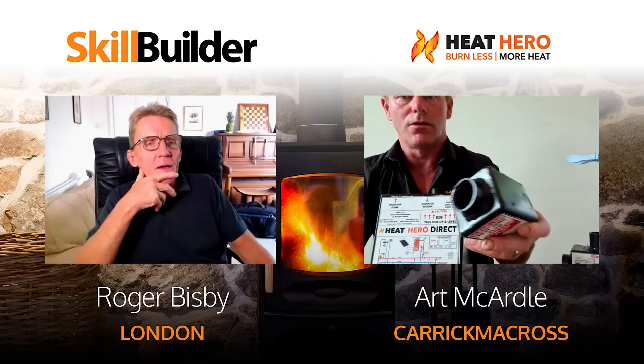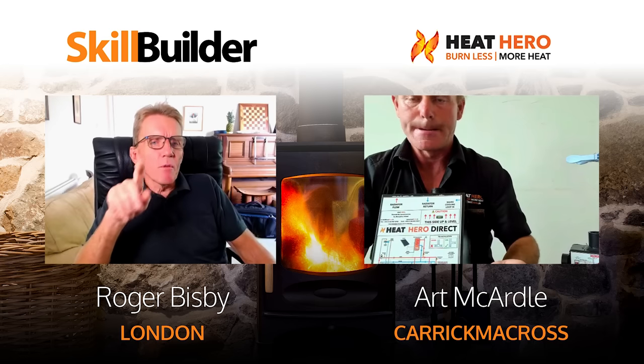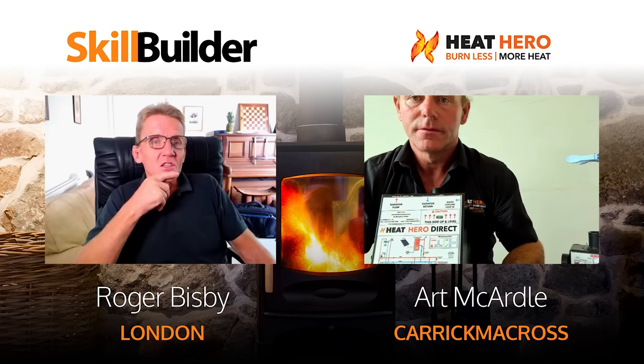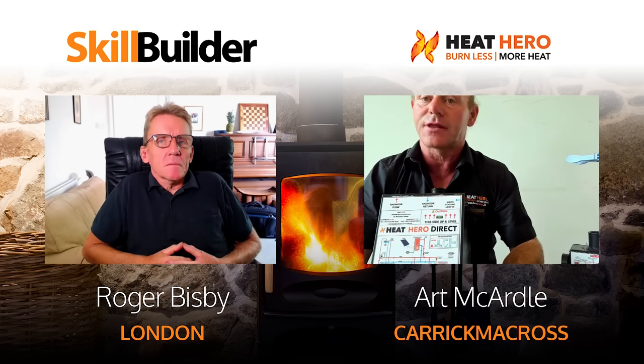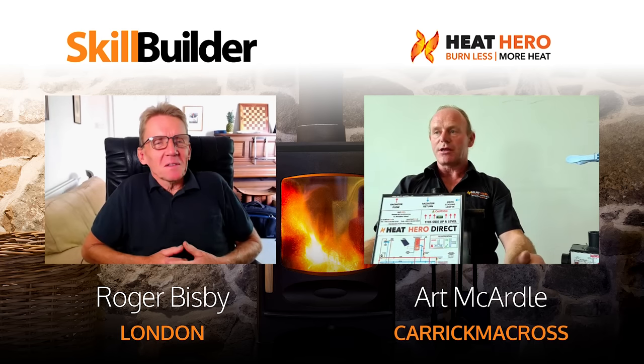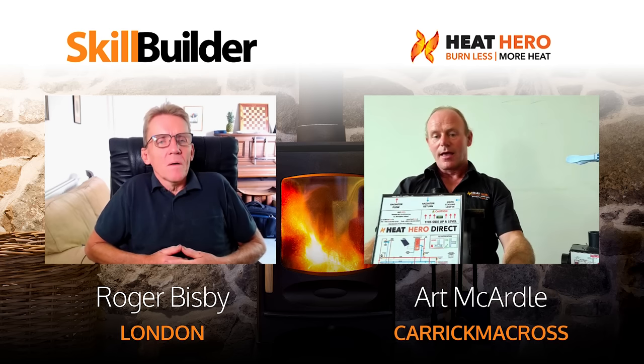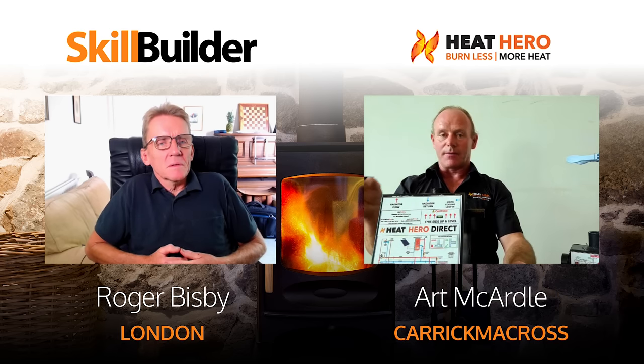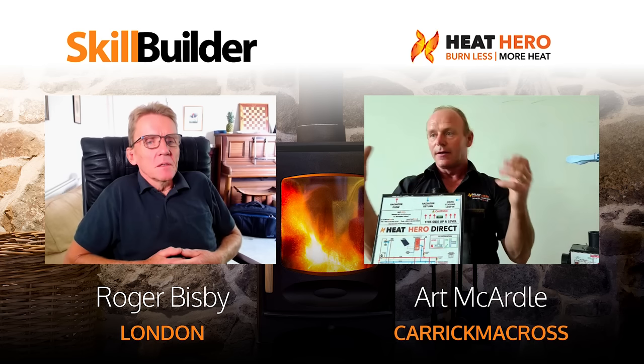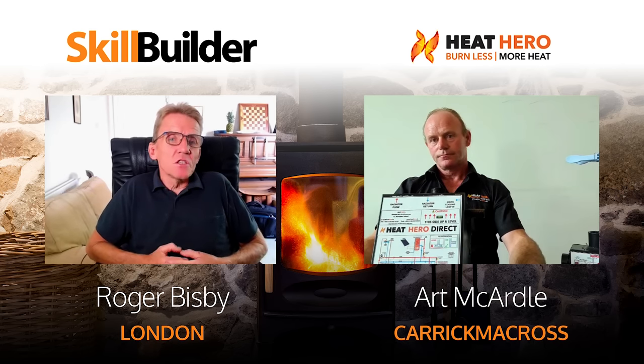It's important to tell people never put a valve between the solid fuel boiler and the open vent. In one house we found someone had done exactly that - people are relying so much on solid fuel that they're doing anything they can, including capping off their open vent to stop the pumping over. In the colleges in this country they're still teaching the same old approach - injector tees on the return, pump on the return - and plumbers come out and one job might work okay, the next is pitching over, and they're putting in their own workarounds. The Heat Hero does away with all of that.